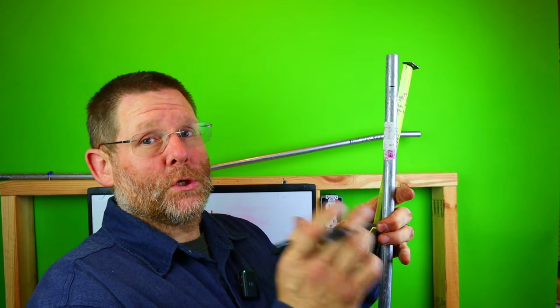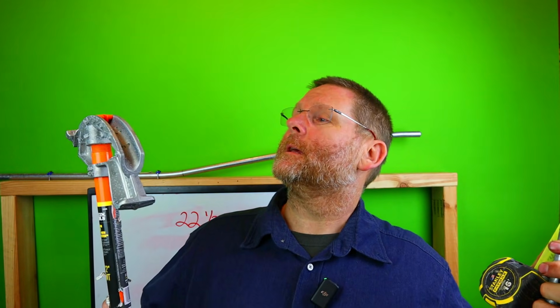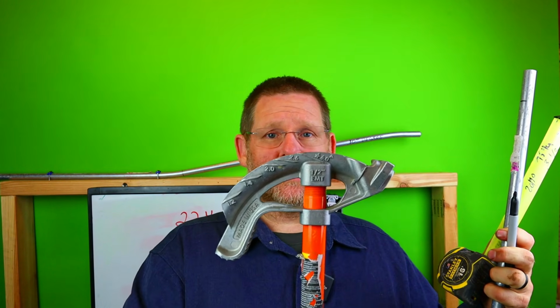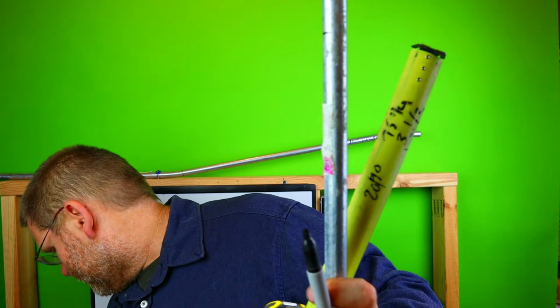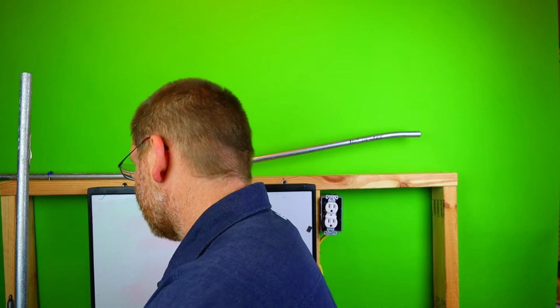And what are we doing? We're doing a 4-inch bend. So we know that 22, let's look at the bender. All right. The bender says 2.6. So what does that mean? Well, let's get the whiteboard and show you. So we've got our 2-inch mark. Now we've got to know where the next mark goes.